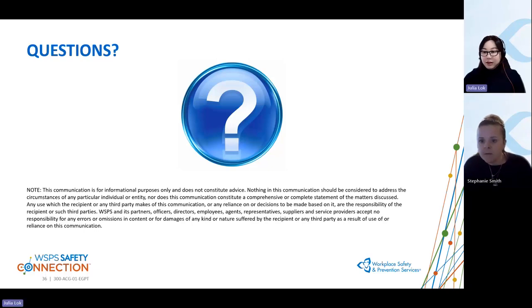Do the operators also lock them, or only maintenance? So you've got pumps requiring maintenance—in your process, the person working on the equipment would definitely need to be locked out. Each person working on that equipment would need to lock it out. So if you've got two maintenance people, both have to attach locks, or you have to have a group lockout procedure. There are times where a piece of equipment is down and it's going to take a while for maintenance to get to it, so you may put something like a shop lock on, but again your program has to encompass how you lock that out.